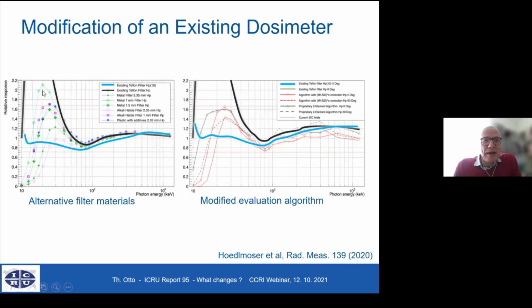And then the lighter curves in this plot are the use of different filter materials on the dosimeter than the standard Teflon filter. And on the right side, there are modified evaluation algorithms because the dosimeter has 2 detectors and one can change the ratio of evaluation between these 2 detectors. And you see that they improve the situation somewhat until a certain energy where then it cuts off still. But this is, I would say, first work which has been done recently. And before these new quantities become legally binding quantities, there will be enough time to do more work of development and research to adapt dosimeter types to them.